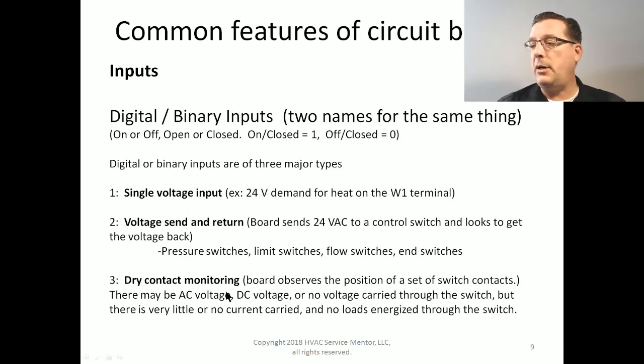What dry contact monitoring means is that the control board observes the position of a set of switch contacts. Now, on the wires going through the switch contacts, there may be AC voltage, there may be DC voltage, or there may be no measurable voltage at all carried through the switch. Either way, there is very little or no current carried through the switch, and no loads are directly energized through that switch. That's what we mean by dry contact monitoring.